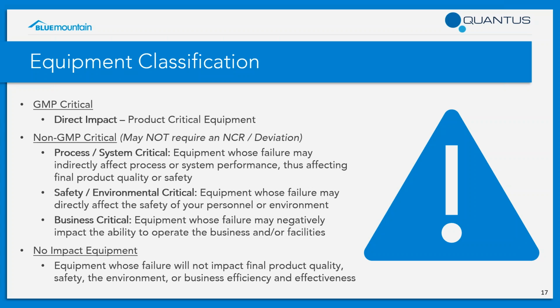When we get into non-GMP critical devices, we tend to like to break them out a little bit further to make any investigations a little bit easier. So a process or system critical device, going back to that autoclave jacket pressure example. A lot of autoclaves have steam that is fed from the jacket into the chamber. So if the jacket pressure was off a little bit, it could affect the chamber pressure, which could affect product quality output. So it's going to be an indicator to look into a couple other instruments on the device.